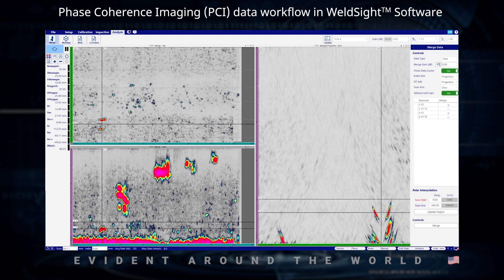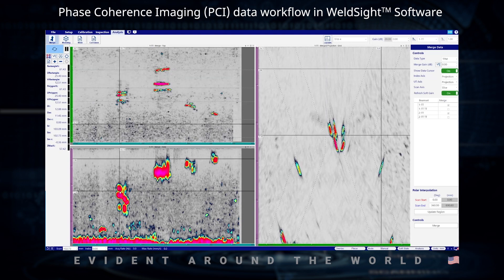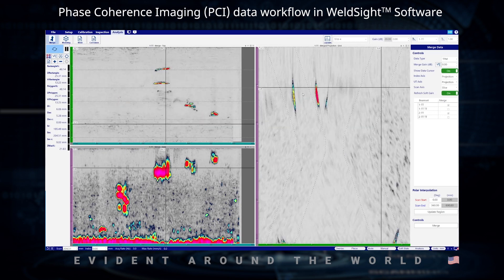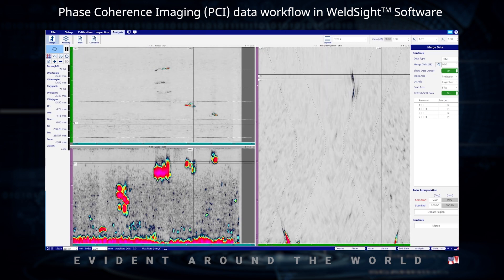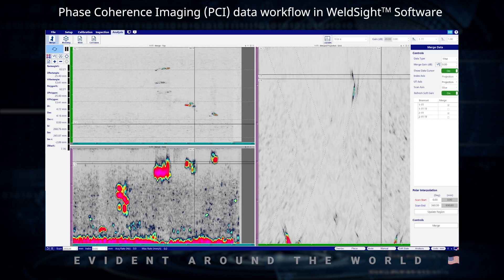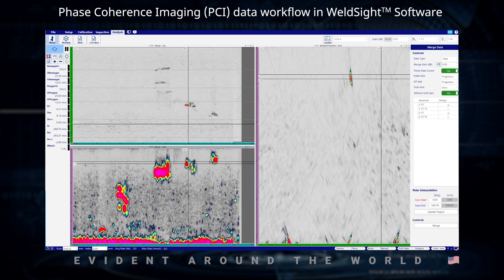Just rolling through the data here, we can see we've got a heat-affected zone crack coming up on the far side, running along root penetration here, likely a sidewall lack of fusion, and in this area there's actually a nice cluster of porosity, which PCI really highlights and excels in. You can see each individual pore as we roll through that data.